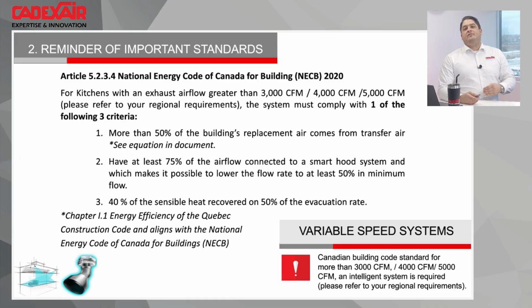The second point, if you need to have 75%, and that's I will say the most used one in the business. When you're over your CFM trigger, you need to have at least 75% of the airflow connected to a smart hood system, which makes it possible to lower the airflow by at least 50%, to the minimum flow. So in a few words, if you are over the standard, you need to be able to modulate your airflow down to 50%.